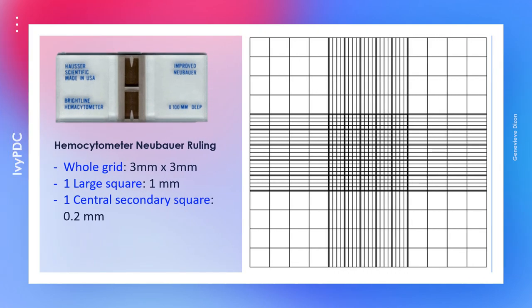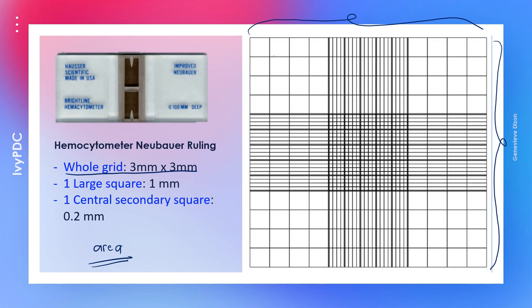Knowing the measurements of the grid is important for computing the area in the total cell count. The whole grid is 3 mm by 3 mm, meaning each large square measures 1 mm each. The central large square is divided into 25 secondary squares, and each of these secondary squares measures 0.2 mm.